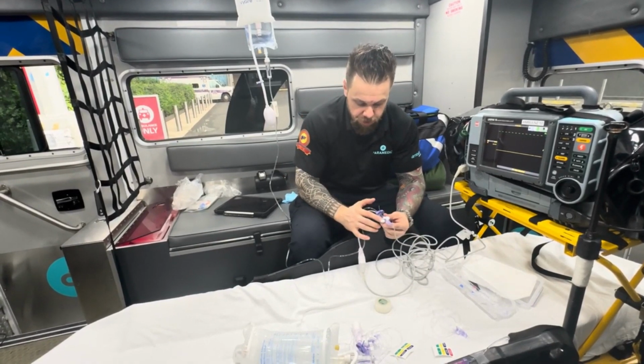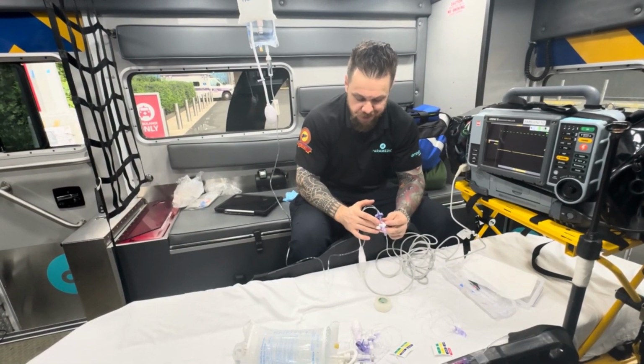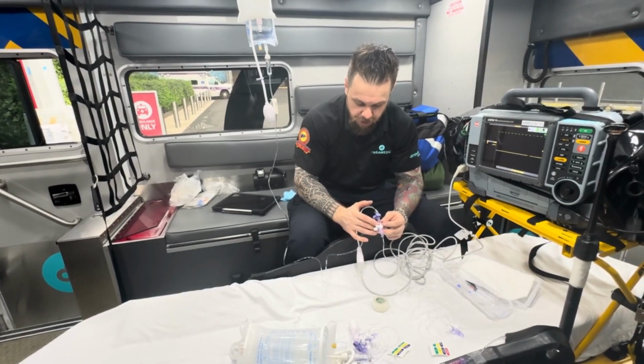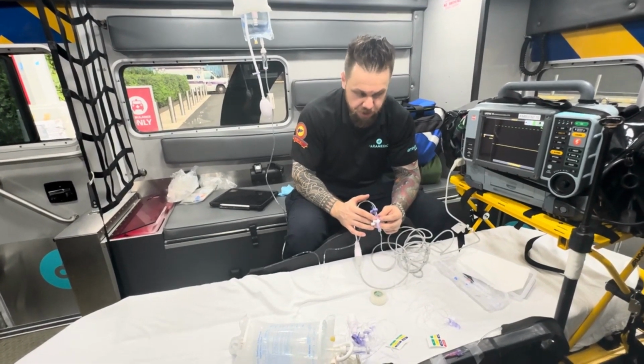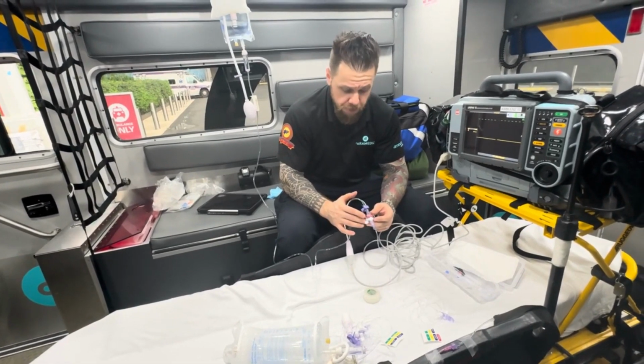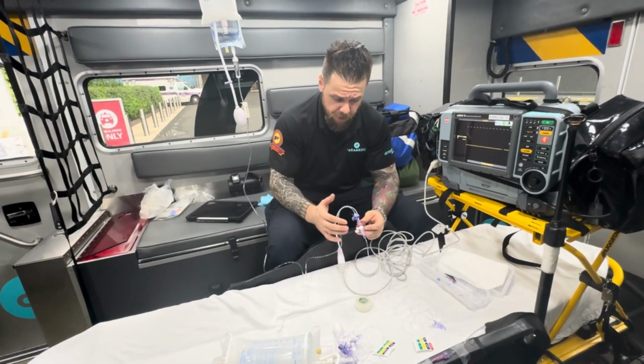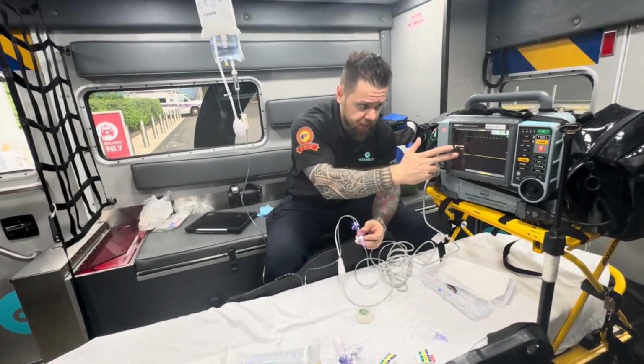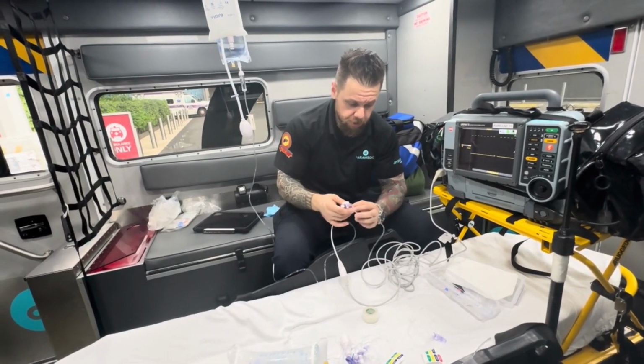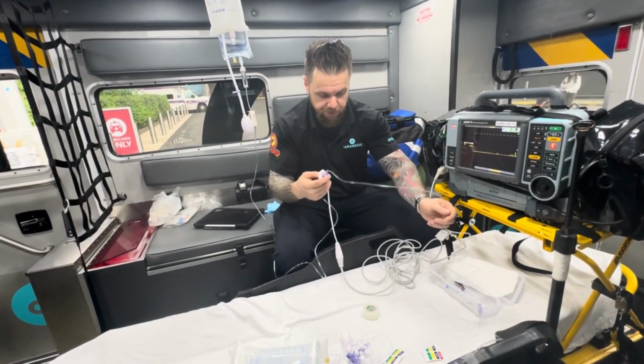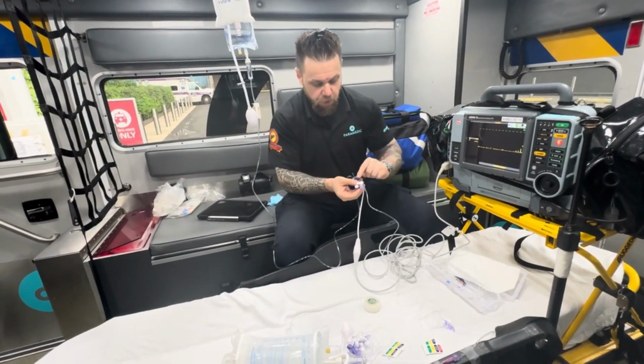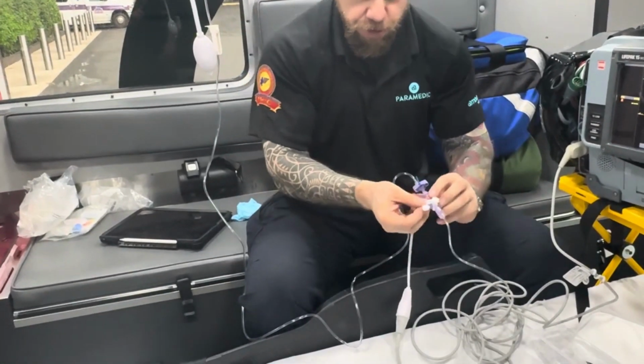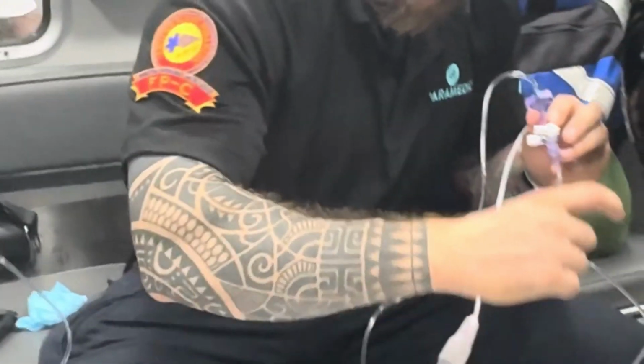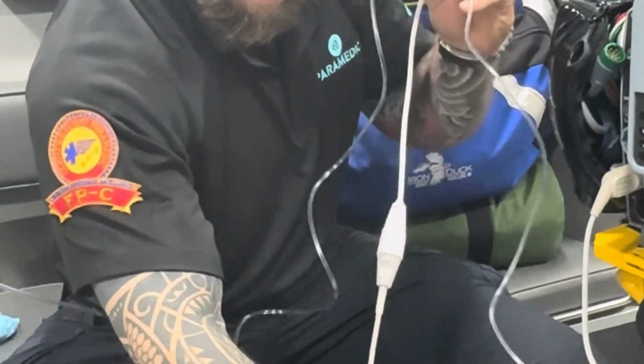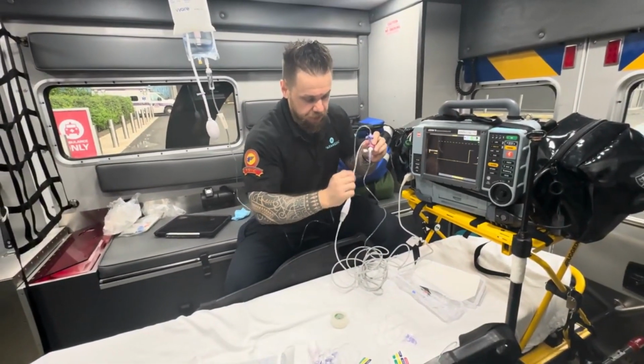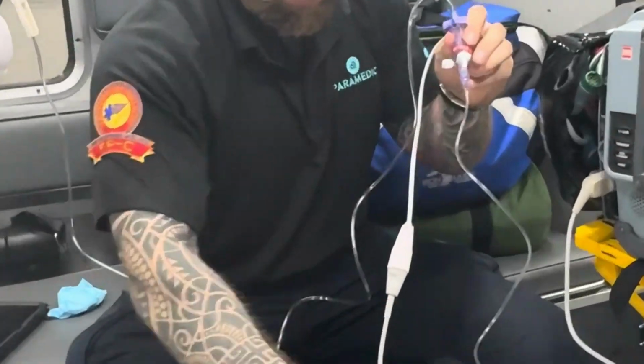What the transducer does, it's a strain gauge. It's measuring the fluid pressure and converting it to an electrical signal. So it's measuring the pulsations of the fluid in the artery and converting it directly to the electrical signal. What you're going to do is as follows. On the transducer itself, you're going to find this port, and where it points to, that portion is off. So it's off to the side, and you notice how all of this is going to the patient now, right? So I'm going to turn this off to the patient.